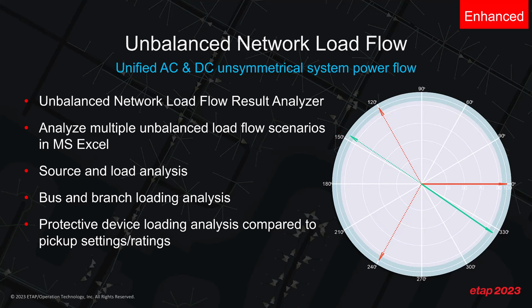And one of the other things that it's able to do is it also allows us to compare the protective device loading compared to its pickup settings and ratings. So when you have a trip unit and you have a long time pickup on that trip unit, we are also able to compare the unbalanced load flow results along with the trip unit long time settings, and not just compare it with the breaker frame ratings, which can be different in many situations. So let's see the Unbalanced Network Load Flow Result Analyzer in action in ETAP 2023.